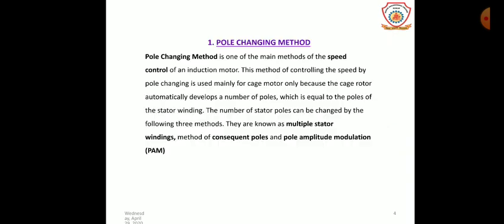The pole changing method is one of the main methods of speed control of an induction motor. This method of controlling speed by pole changing is used mainly for cage motors only, because the cage rotor automatically develops a number of poles. Continuous smooth speed control is not possible by this method.